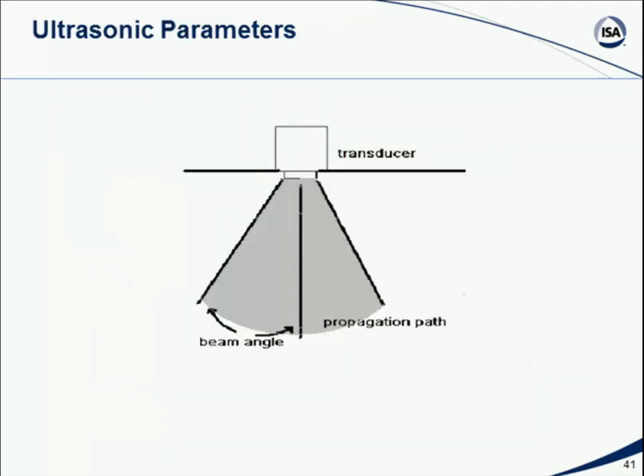So in a lot of cases, we'll use ultrasonics to take a measurement, which is really a measurement of distance from the top of the tank down to the surface we're looking for. So we put an ultrasonic transducer at the top of the tank, and it will, on a regular basis, send out a sound pulse and then listen and time and count how long it takes for the sound pulse to come back. Now, there are a variety of things you have to consider when you use ultrasonics.